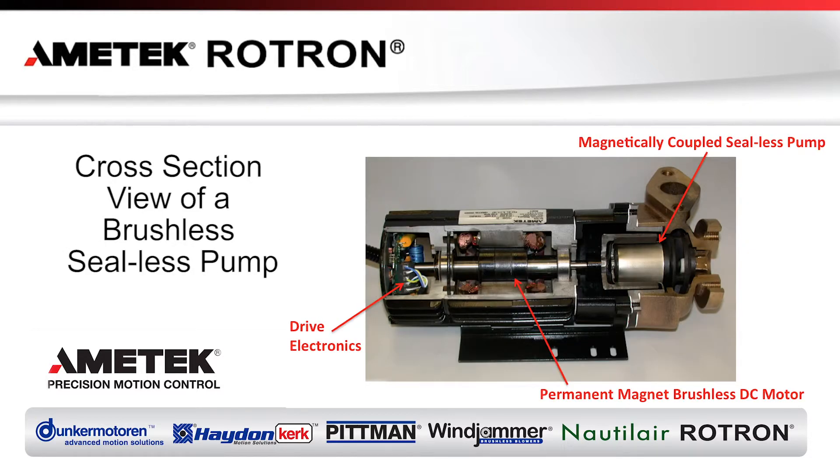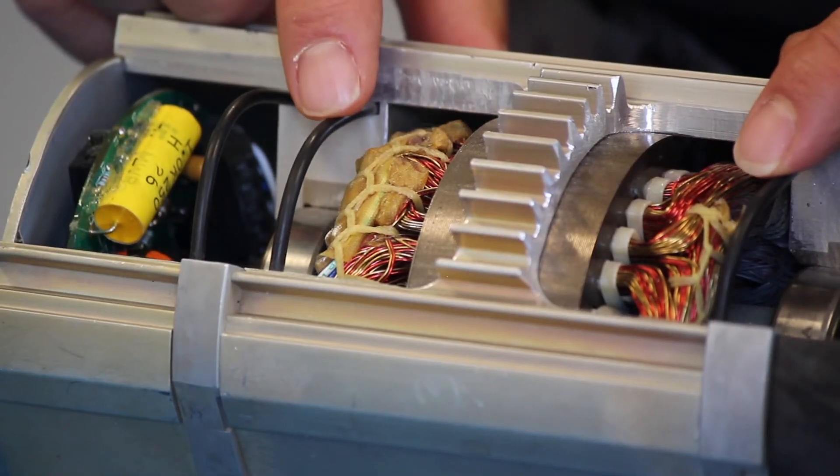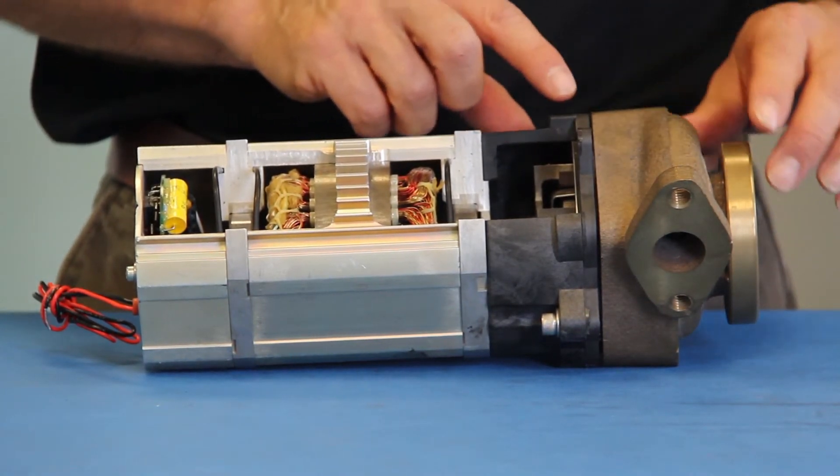This cutaway view of an AMETEK Rotron pump shows the key features which have been discussed: the electronically controlled permanent magnet brushless DC motor, with O-ring seal construction environmentally sealing both the electronics and the motor compartments, the double sealed bearing system, and the magnetically coupled sealless pump head.